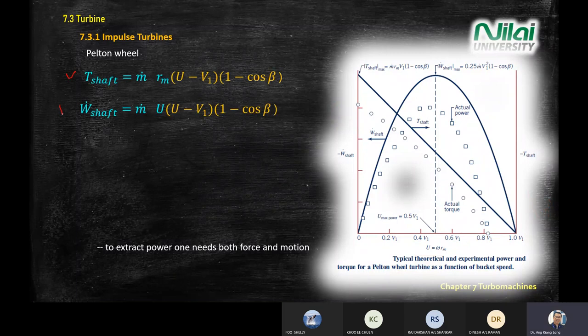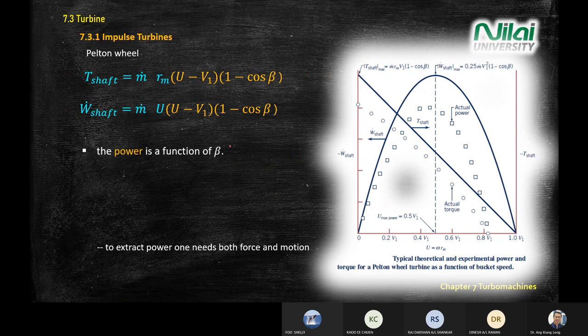A typical design value for beta in a turbine is 165°. This is the ideal starting value; different manufacturers adjust beta according to their operating conditions. For beta = 165°, the term (1 − cos beta) equals approximately 1.966.